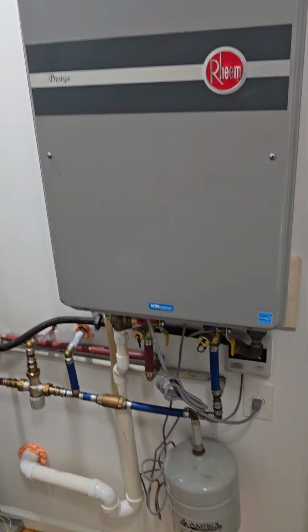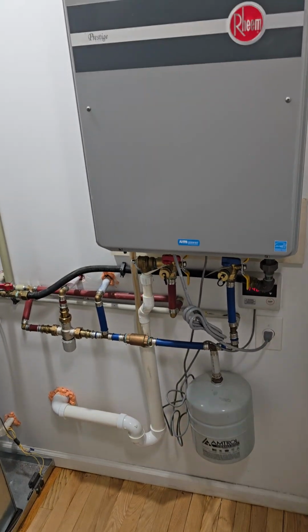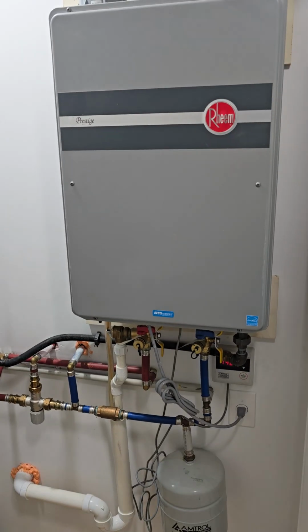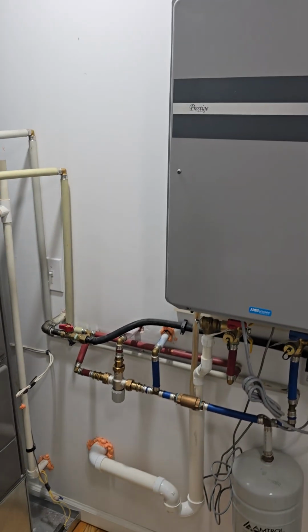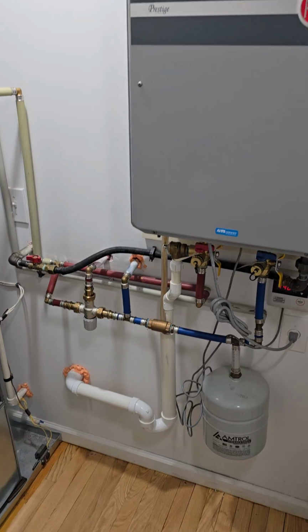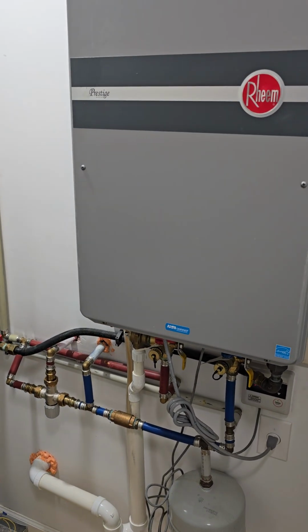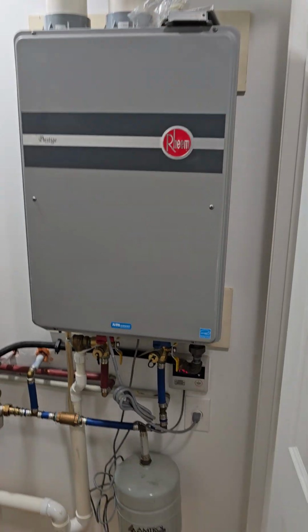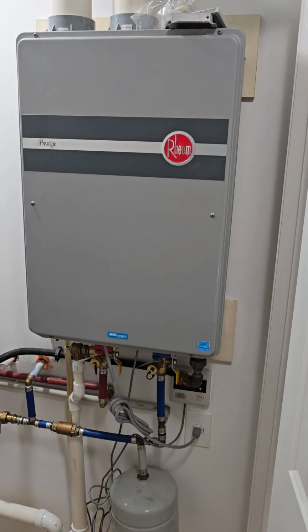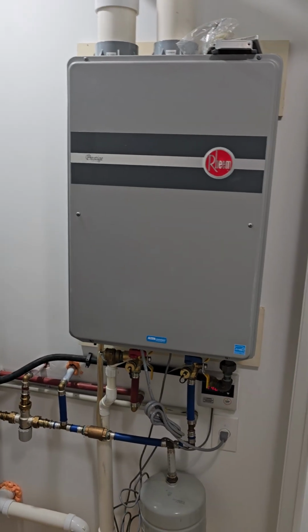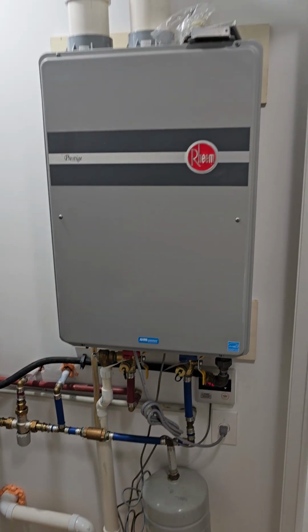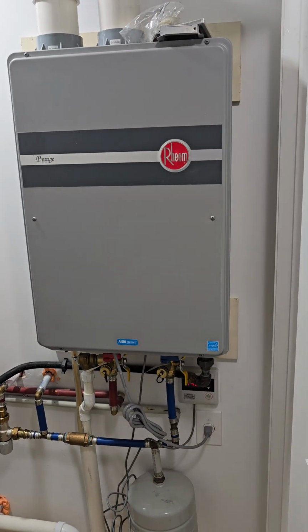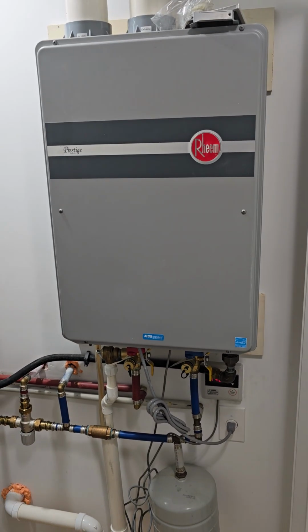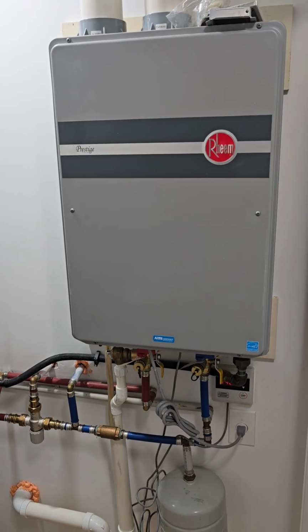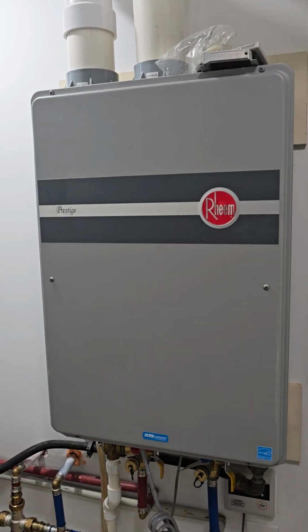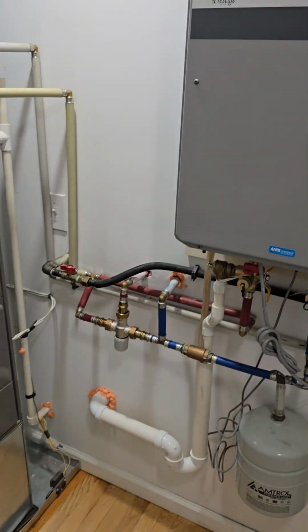He said the gas pressure regulator inside the unit could be improperly adjusted. There are air cleaners in here, water filters in here -- a whole bunch of components to this system, and he said they have to be maintained every year. This one, he believes, came with a 15-year warranty on the heat exchanger, the part that always dies -- but only if it had annual maintenance, including flushing and descaling.